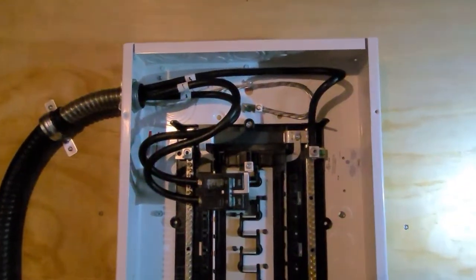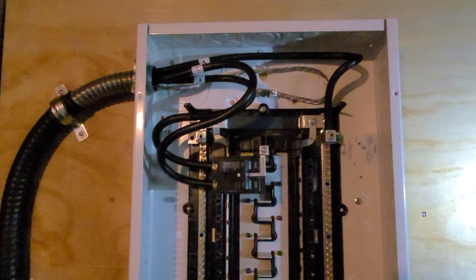This is how it looks after we install the backing plate and electrical panel on the wall. And you can see we also terminated one side of the service cable into the electrical panel. There are a couple of things worth taking a look at here. First is the neutral bond jumper screw. We do need this at the main panel, so basically we connect the neutral bar to the panel itself. But this is not required at the sub panel. Actually, you cannot have the jumper screw in your sub panel.